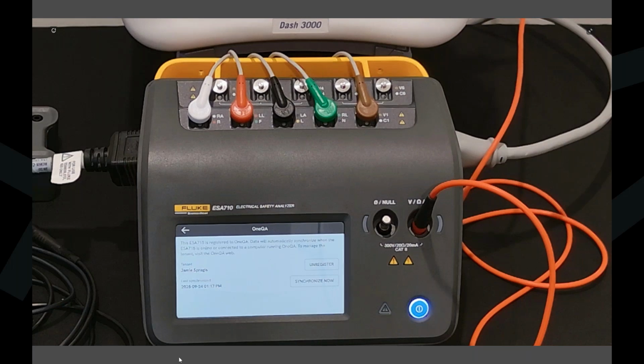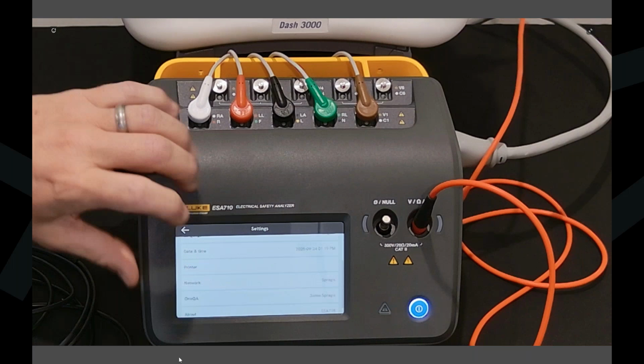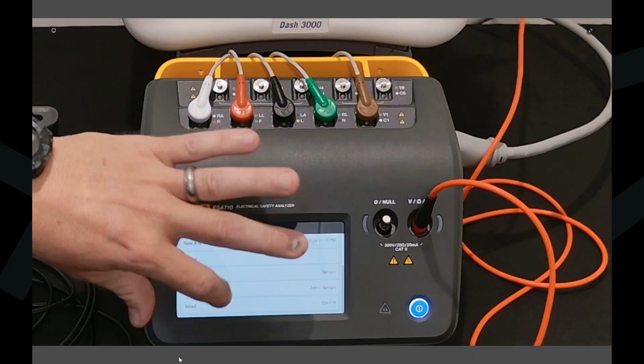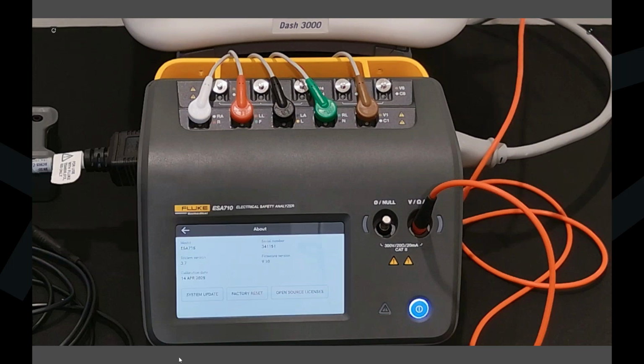Lastly, about the unit - for quality assurance, we have the calibration date on the instrument. Not only is the calibration date on the instrument, but the moment you tether back into your PC, that instrument shows up on all the tests you do along with your calibration date. That's a very important piece of data that a lot of regulatory bodies like to see - is your test equipment calibrated.